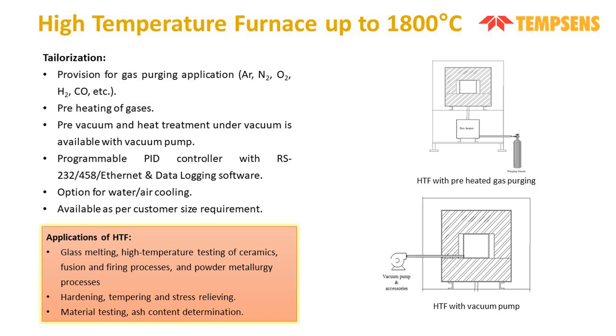Next, coming to the tailorization in high temperature furnaces. In high temperature furnaces, we can introduce gas purging for argon, nitrogen, and oxygen. Then we can preheat the gases for the purging, and we can introduce vacuum and other accessories, such as vacuum pumps. We can introduce the same programmable unit in this furnace, and we can customize the size according to the customer requirement. Basically, the HTF are used in the areas of glass melting, high temperature testing for ceramic, firing processes, powder metallurgy, hardening, material testing, etc.